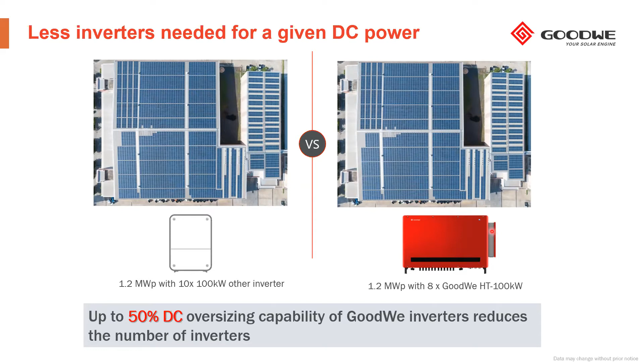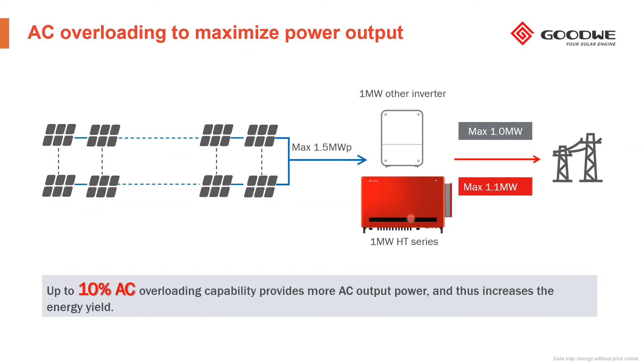The AC overloading allows the inverter to feed into the grid a bit more energy than the nominal one. Obviously, that happens as long as we have enough energy in our input. And that is combined with the previous feature that we have seen, the DC oversizing. So the combination of those two features can make us feed more energy than the nominal one to the grid. Of course, if there is a legal requirement that we cannot provide more than the nominal one, we can set up properly during the commissioning the 100% of the energy in the settings of the inverter, right?